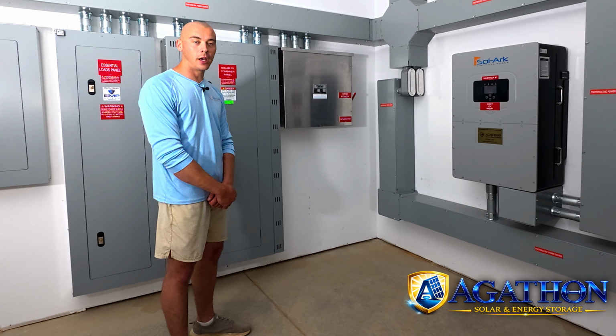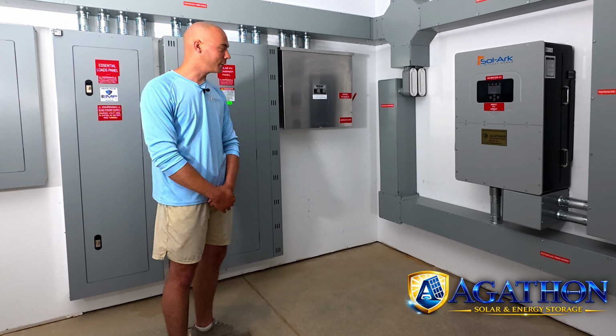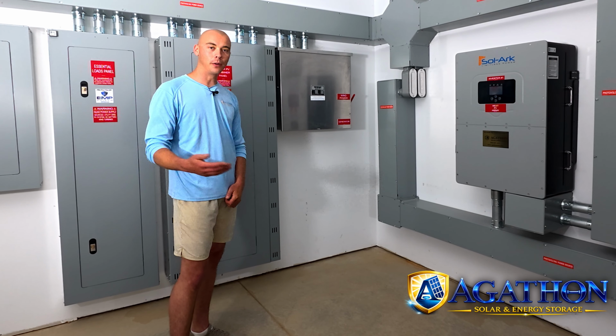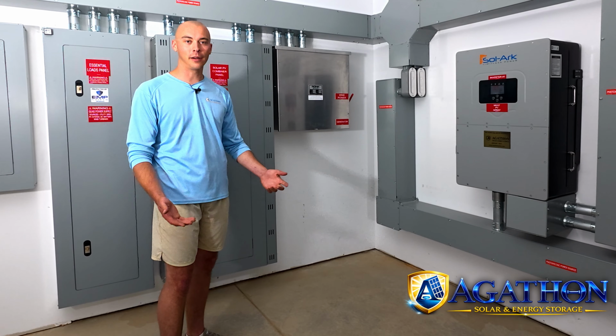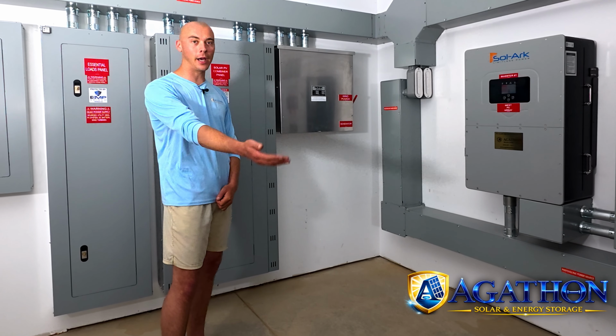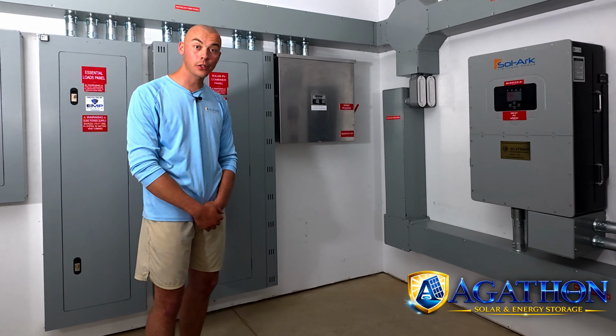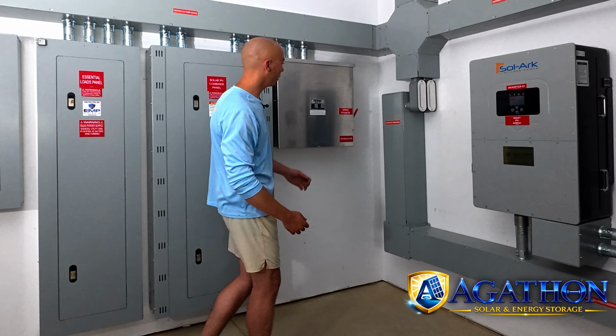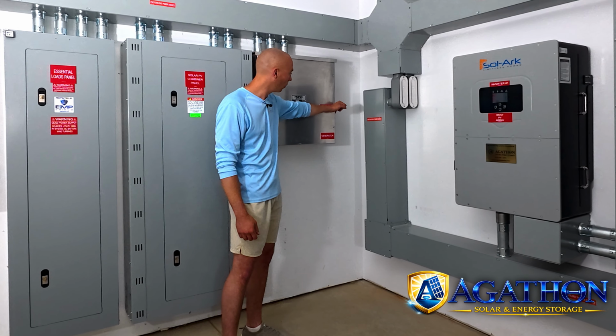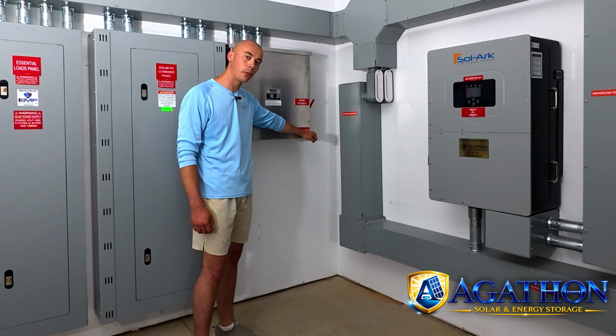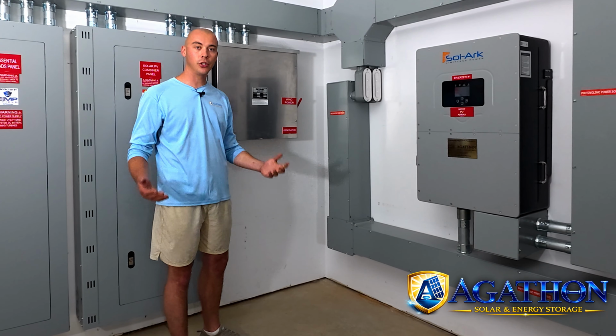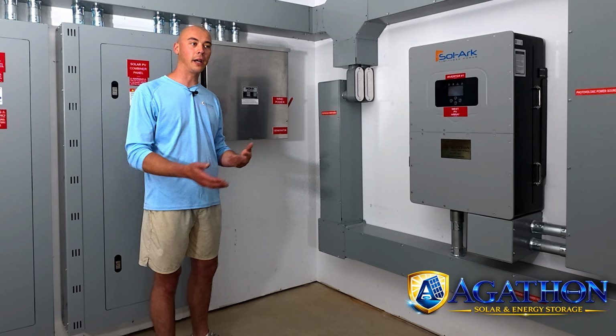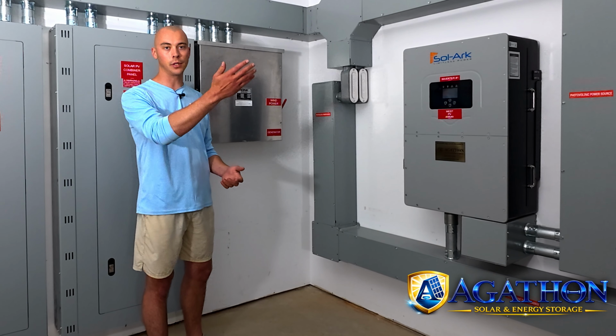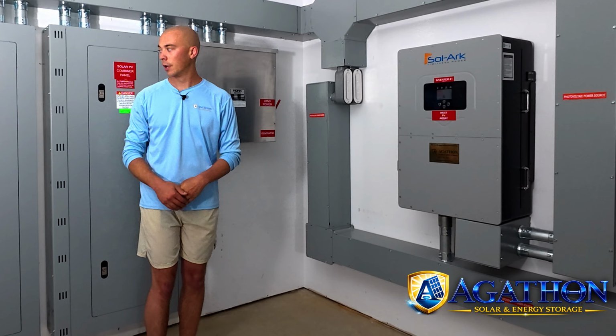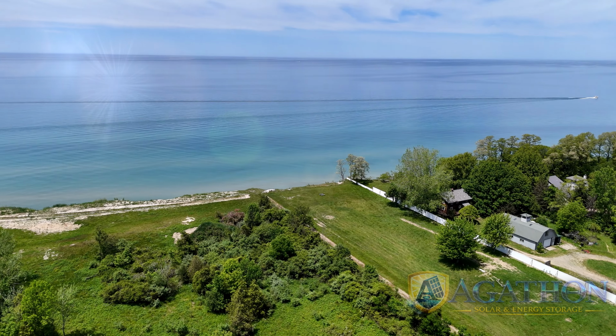In the event of poor weather, which we see here in Michigan, whether it's low sunlight or not a lot of wind production, and the batteries are at their depth of discharge, you can switch this manual two-pole transfer switch down to the generator port. That would allow a generator to provide backfeed power to recharge these batteries and provide power to the loads of the building.